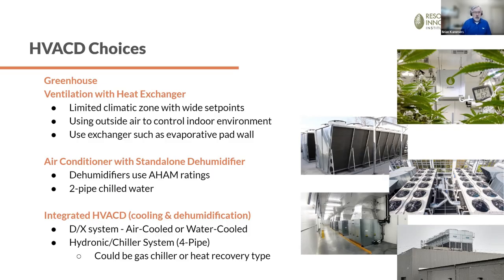Your house has an air-cooled condenser on it, but they can also be water-cooled. And then Rob asked me the question about what size do you go to chilled water. When you get to, say, 400 tons, you start looking at chilled water systems that are 4-pipe. 2 pipes are chilled water, 2 pipes are hot water.